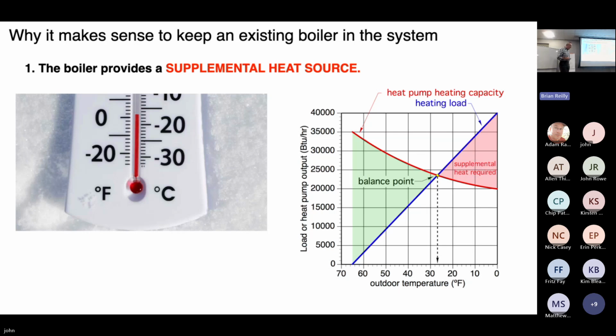We've talked about performance of any air source heat pump. Basically, the heat pump capacity goes down as the outside temperature goes down, but the heating load goes up. And I'm sure most of you have probably seen this balance point type graph. So there's some outdoor temperature, in this case maybe about 26, 27 degrees, where the output of the heat pump equals the heating load. And if it gets colder, we need something else to meet that heating load. Now, it could be a wood stove, it could be anything, okay? But we're going to need something else to add heat to the building. If there's a boiler in place, or in new construction, if someone chooses to put a boiler in with the heat pump, that can provide that supplemental heat. Okay, so that's air source heat pumps.